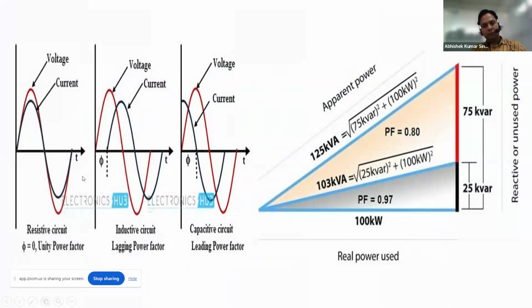Now, as we discussed, if we have to run a load of 100 kilowatt and the power factor is 0.97, then 103 kVA of source capacity is required. And if the power factor is 0.8, then 125 kVA is required. So to run the same load, what are we doing? We are running the same 100 kilowatt of power. But if the power factor is 0.8, then to run that 100 kilowatt we require 125 kVA.